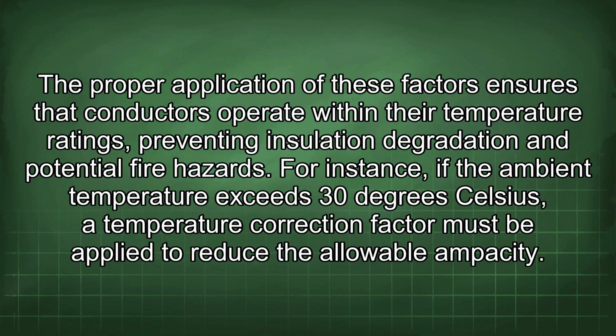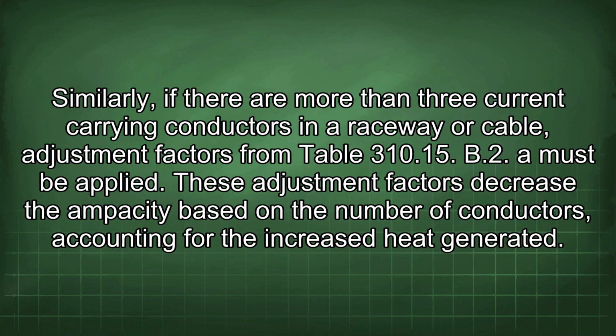hazards. For instance, if the ambient temperature exceeds 30 degrees Celsius, a temperature correction factor must be applied to reduce the allowable ampacity. Similarly, if there are more than 3 current carrying conductors in a raceway or cable, adjustment factors from Table 310.15 B2 must be applied. These adjustment factors decrease the ampacity based on the number of conductors, accounting for the increased heat generated.